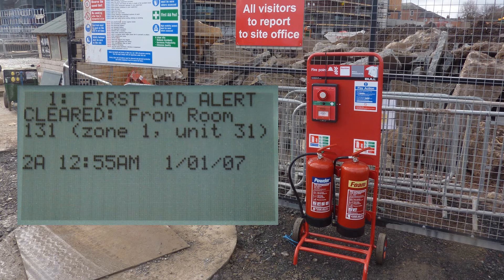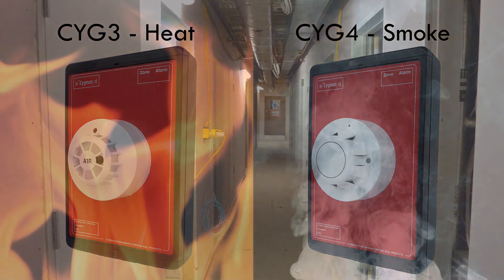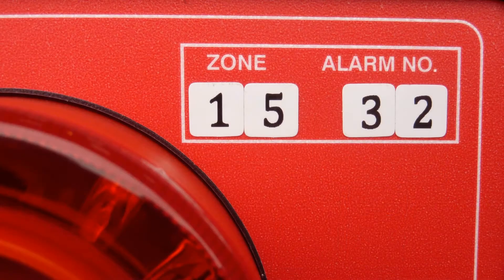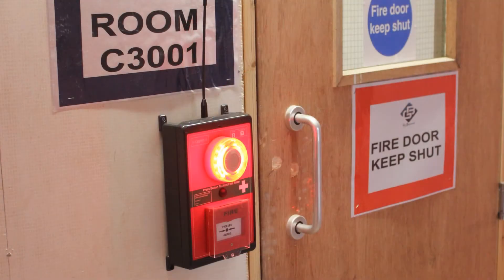This will work in the case of all other alerts and alarms too. The Cygnus smoke and heat detectors are from the Apollo range. These extensively tested and high-quality detectors are used commercially worldwide. They work in the same way as the other devices, using the same Category 1 radio module and battery pack. All Cygnus devices can operate in groups, otherwise known as zones, of up to 32 units. The system is capable of controlling 15 zones in the wider system, operating on the same frequency, but distinguished by different zone addresses. This means a total of 480 devices can be addressed into a single system.